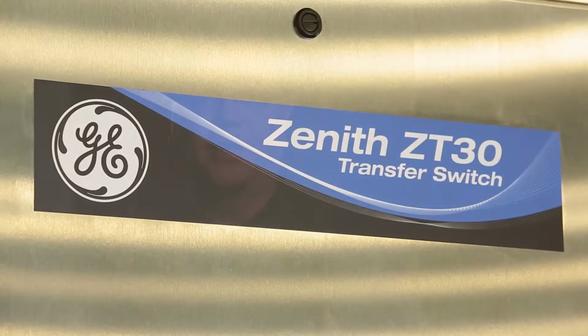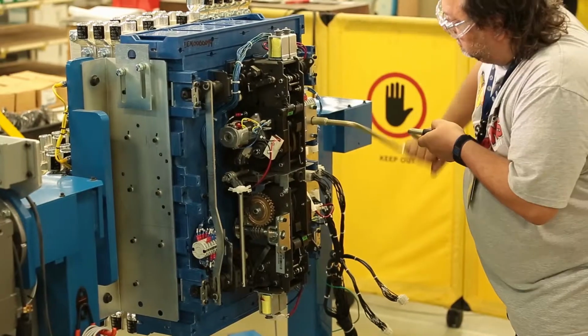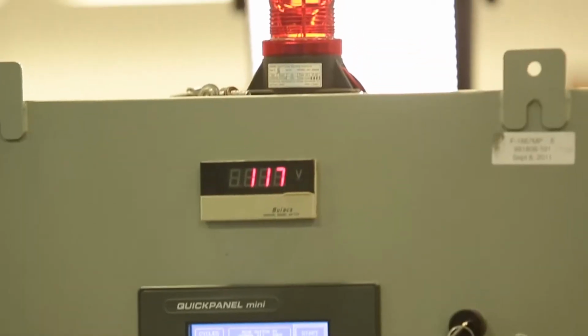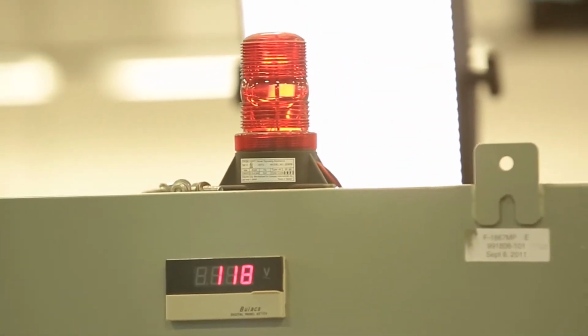The ZT30 gives them the capability to provide real selective coordination. It gives you performance even after a short circuit event, whereas regular UL requirements for transfer switches have lesser requirements for pass-fail. A short time rated product is a product that survives an event.